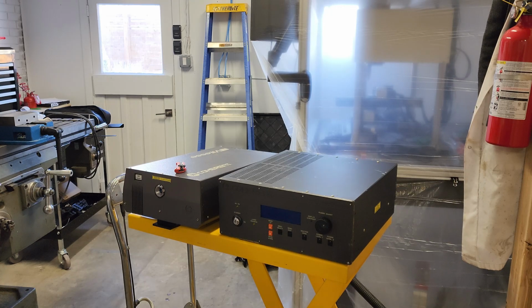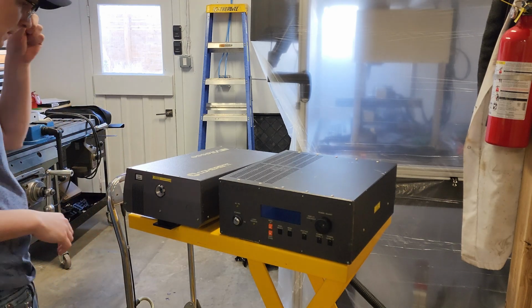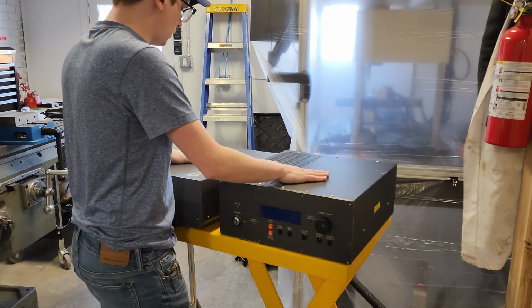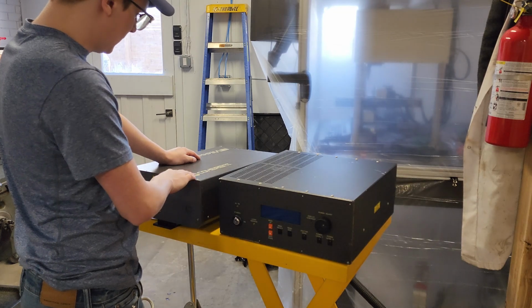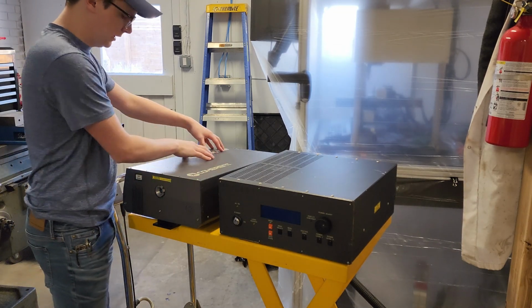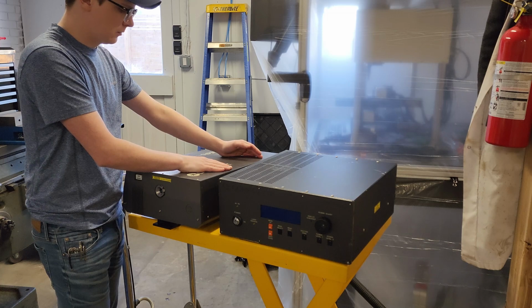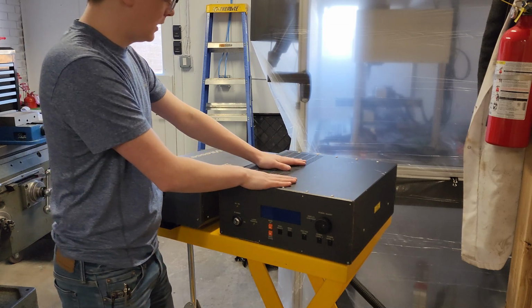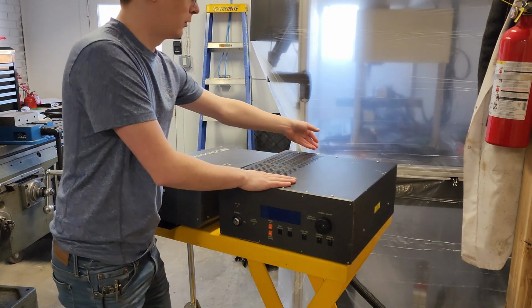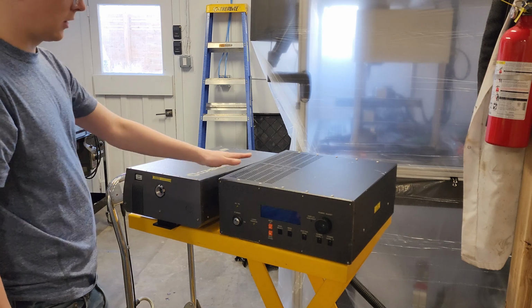This is the Vitesse. That provides the pulses to the amplifier, which is behind us now. This is the control electronics. I don't know exactly what all is in here, but it talks to here a little bit. On this side, I believe, is the green pump laser. On this side is the resonator cavity where the ultra-short pulses are generated. In here is a single pump diode, and it's coupled through an optical fiber through the black umbilical back. And then there's a bunch of cables that connect the laser head to the laser controller.